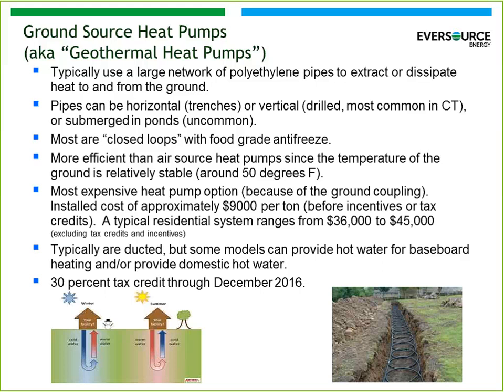These pipes carry water. There is a propylene glycol antifreeze solution that's added into the pipes just to prevent them from freezing. And I know folks here, they hear the word antifreeze and they tend to panic. But essentially, the propylene glycol is a food-grade antifreeze, and you can find it all over the shelves of your supermarket, and even in places like Dunkin' Donuts. It's flavored iced teas, certain types of ice cream, frosting, cake mixes, salad dressings, and my favorite, even Fireball cinnamon whiskey contains some level of propylene glycol. So I think it appears to be a fairly safe type of antifreeze choice for use in ground source heat pumps.